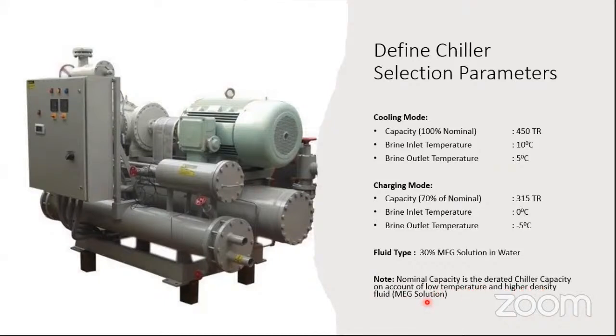So it might be possible that the chiller here was actually a 550 tons rated capacity, and the temperatures you demanded and the solution that you are using to run this brine chiller is making it derate down to 450. So that is also possible. So this is the derated capacity, not the rated capacity. But anyway, the chiller guy will take care of it when you give these selection parameters.